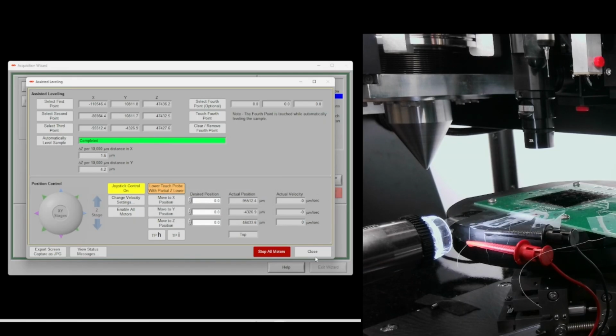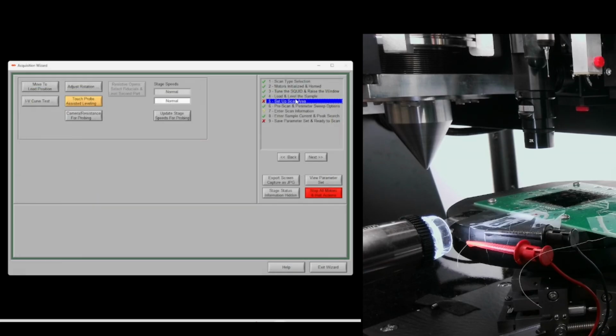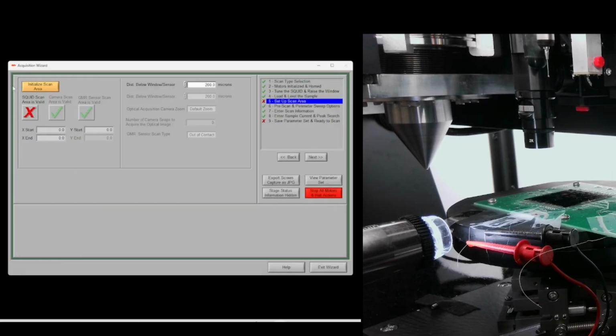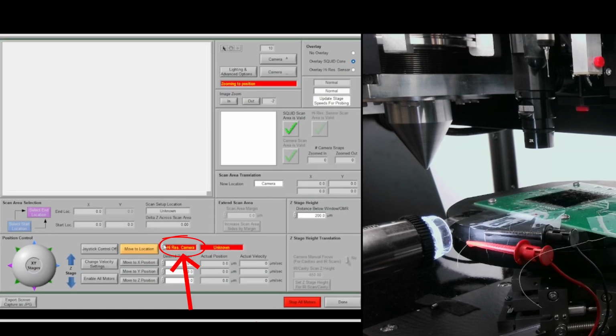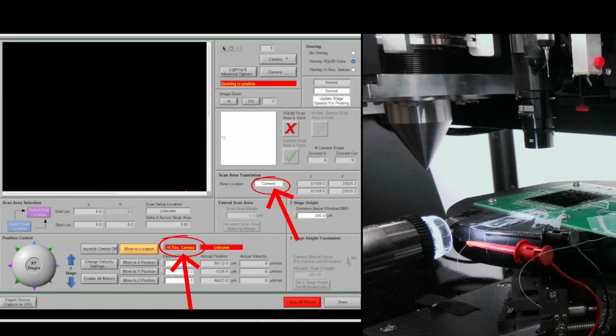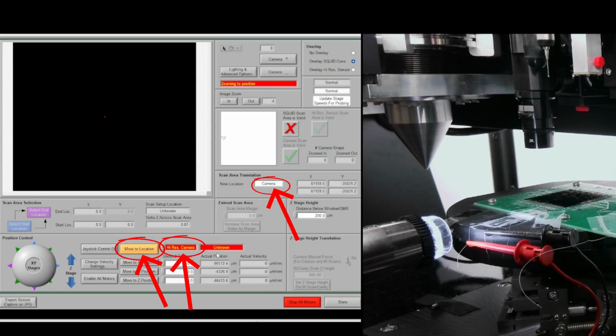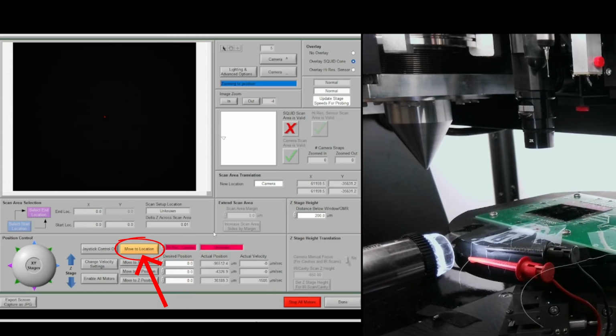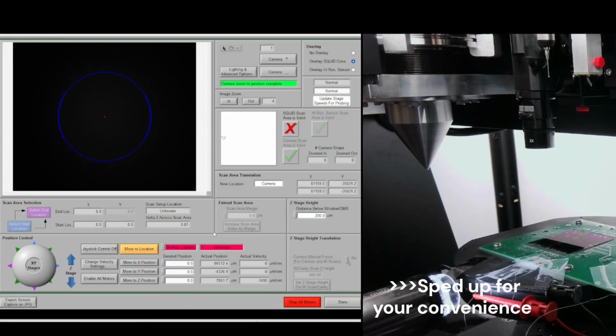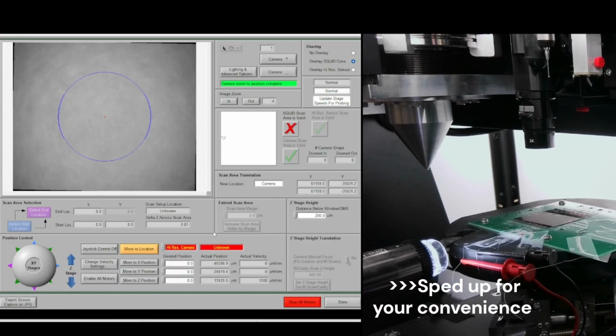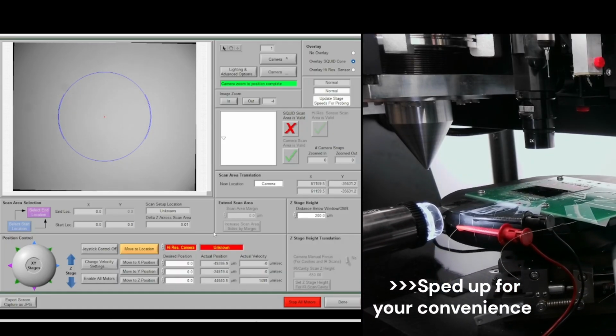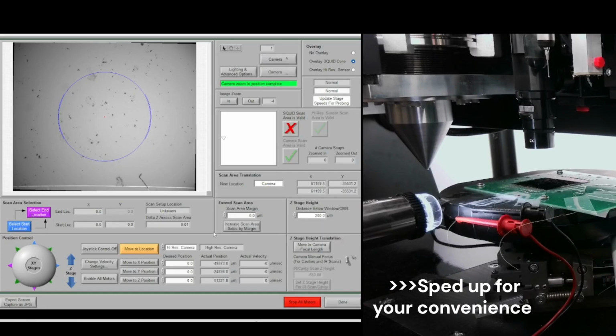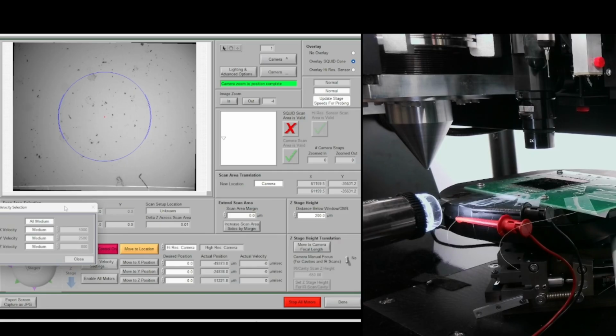Now it's time to define the scan area. We open Step 5, Set up Scan Area, and click Initialize Scan Area. Make sure High Resolution Camera is selected and that camera is selected in Scan Area Translation. Once verified, click Move to Location and let the stage reposition. With joystick control enabled and the speed still set to fast, we locate line 12 on the sample.